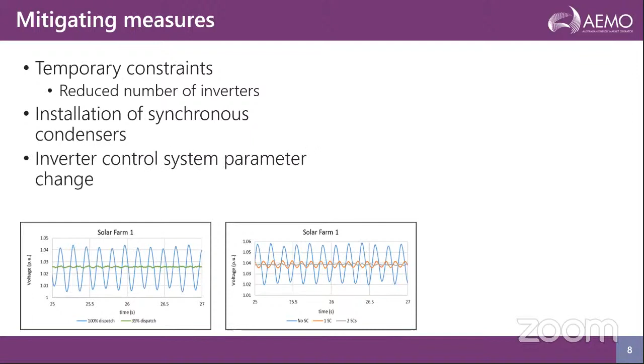The other option which we have implemented in the West Murray area is tuning inverter control. So the option is to tune the inverter control such that they are specifically configured to operate as expected during extreme low system strength conditions. And the third graph on the right shows what you can achieve, which is quite similar to what you could achieve with synchronous condenser. So the solution is to go and tune the control system parameters, which is a very involved exercise.